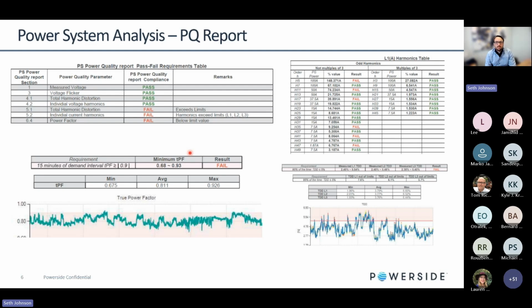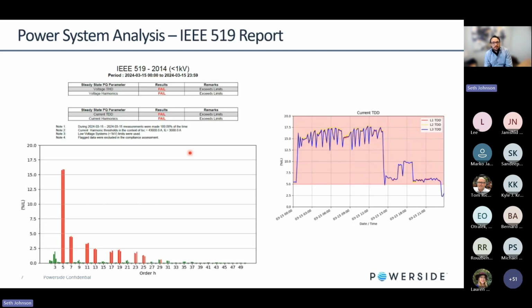Now, of course, in the report, we're going to provide a lot more detailed information regarding the load and all of that. But generally speaking, we're really targeting towards the harmonic distortion, voltage, as well as current and power factor. And one of the things that we offer is an IEEE 519 report. So I talked about the power quality analysis. And one of the things we can do is, if a client has specific targets that they want to hit for harmonics compliance based on EN 50160 or other compliance standards that are out there, we can easily do that.